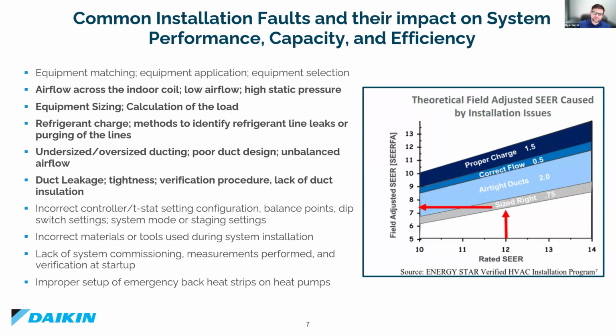All right, so the common installation faults, and I have a lot of empathy for installers. I've installed equipment. I know how it feels to be in a 130-degree attic on a hot summer Georgia day. When does most of our equipment get replaced? During the summer months. When is the most safest time for being in the attic? Probably not during the summer. So there's a lot of confusion with using the right materials. I truly have empathy for the installer and what information they have and what they are able to do.